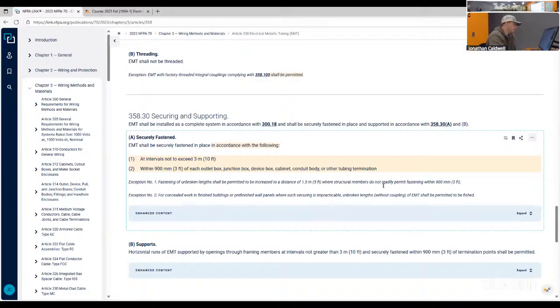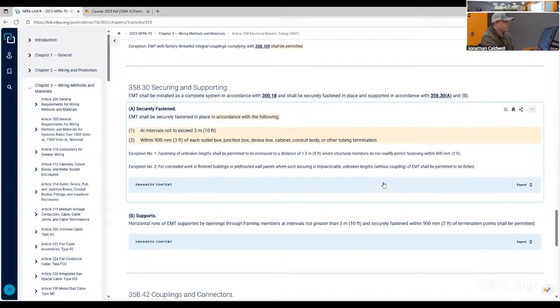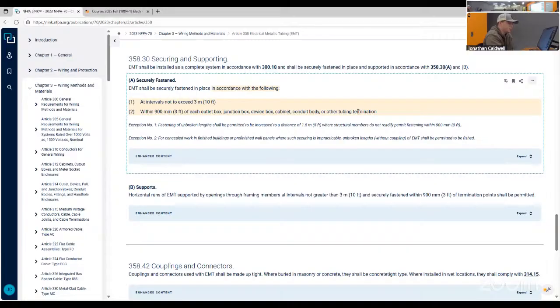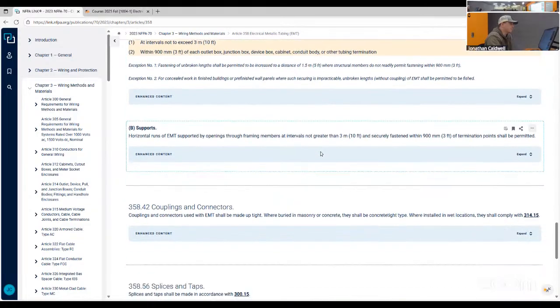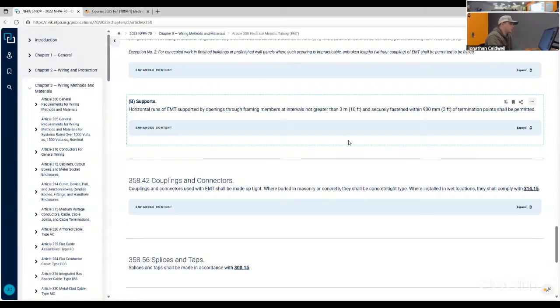Securing and supporting: fasten in place in accordance with the following, at intervals not exceeding 10 feet, and then within 3 feet of each outlet box and so on. Obviously EMT is steel or metal, so it really doesn't bend. But I will say if you're using aluminum EMT, try and support it more often, because even once you get number 10s or number 12s in the 3/4 or half inch, it starts to kind of bow a little bit. So just a recommendation there. And then supports for horizontal runs, 10 feet, obviously.